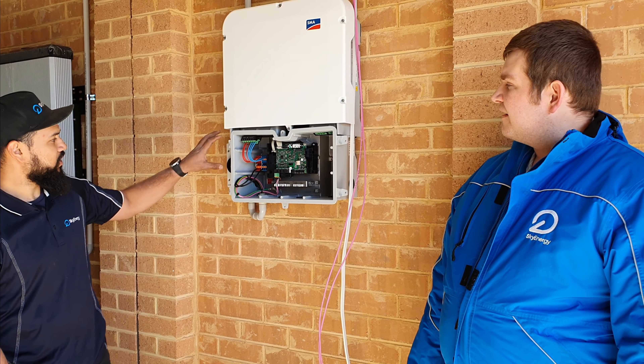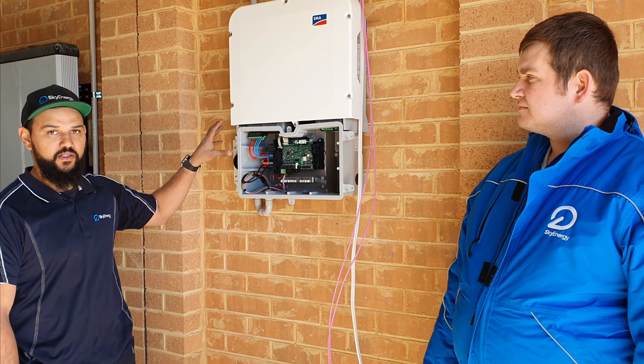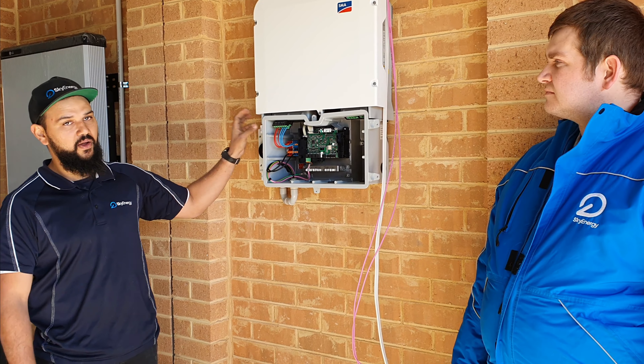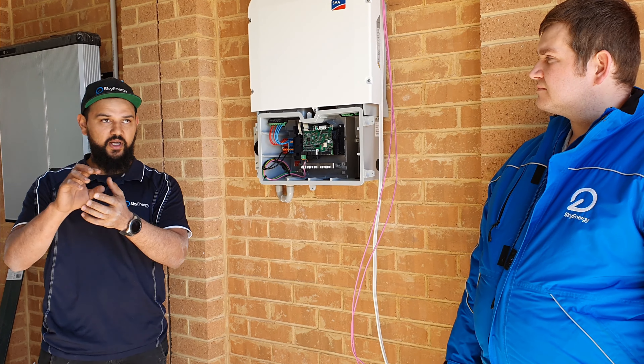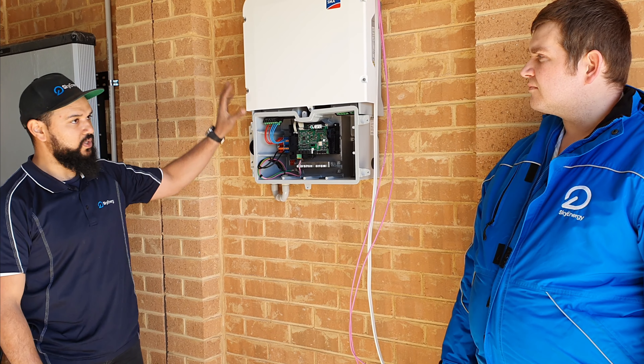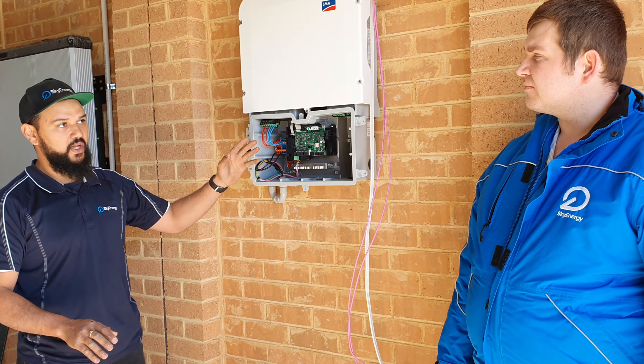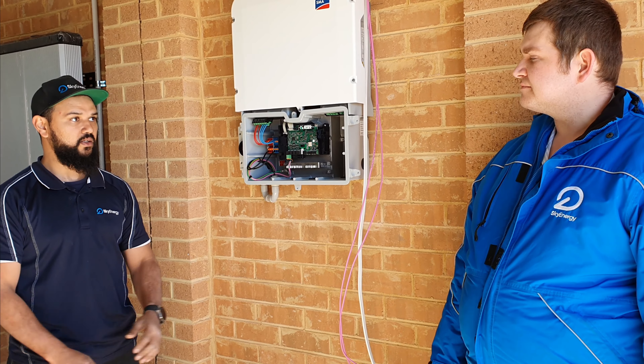Basically the Sunny Storage will stop taking power from the grid once it realises the grid has gone down. It'll actually start discharging the battery power into the house instead. And it's got a safety mechanism which switches out the grid, so no one on the power lines gets injured if they're trying to fix it. Everything's built in — the customer doesn't have to flick a switch or anything. Power goes out, a couple of seconds later everything's back on again, and the solar and batteries are now running the house.